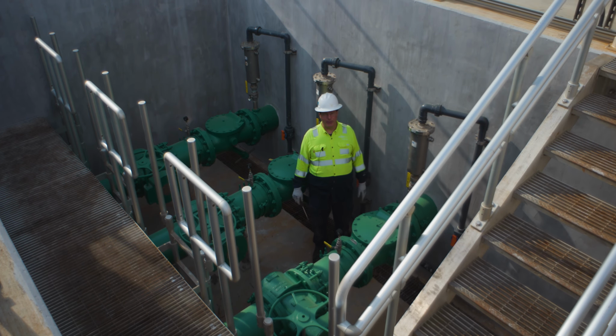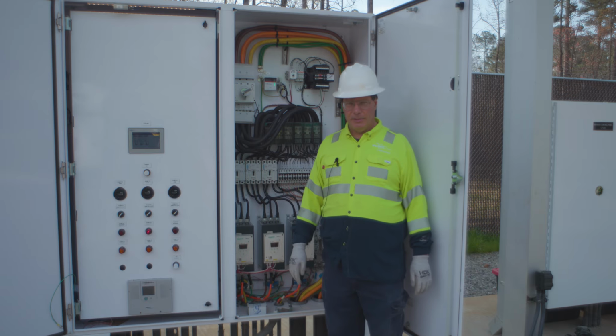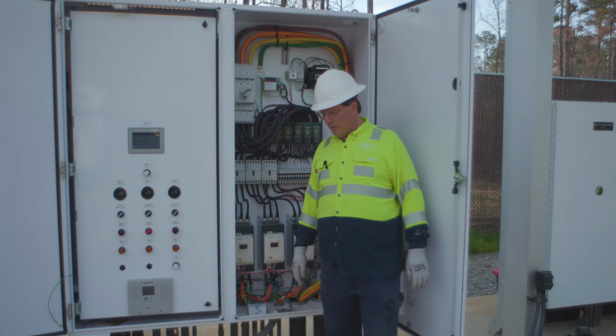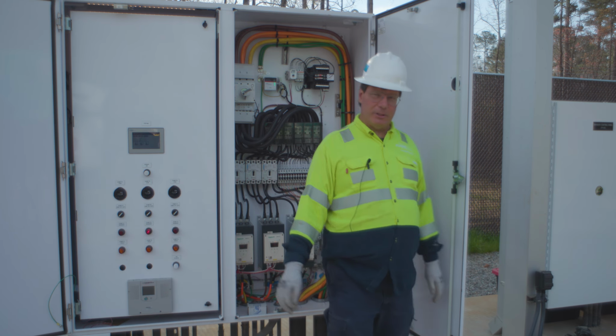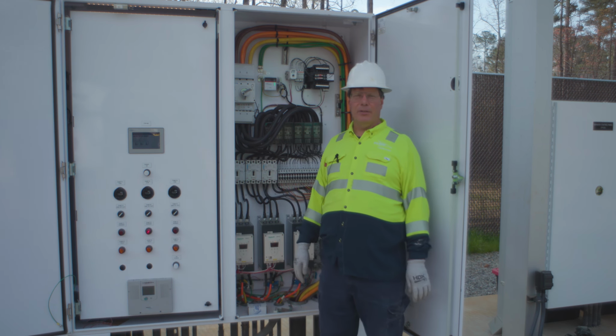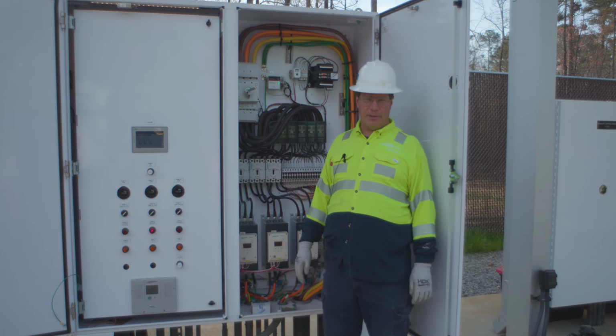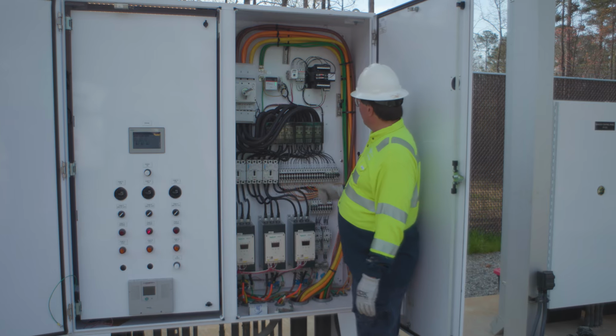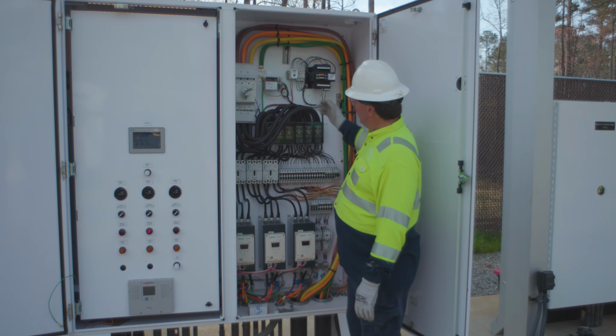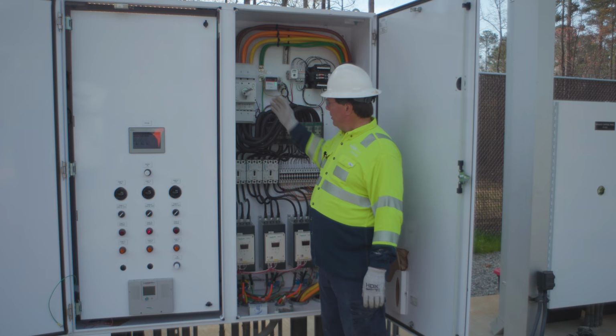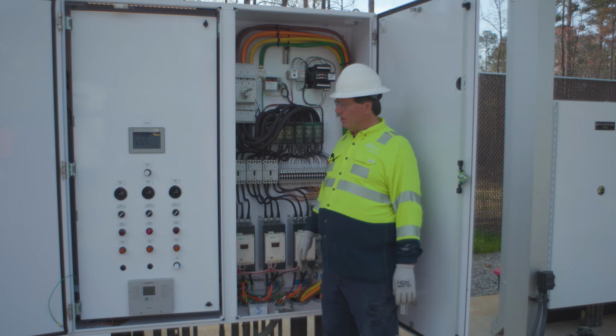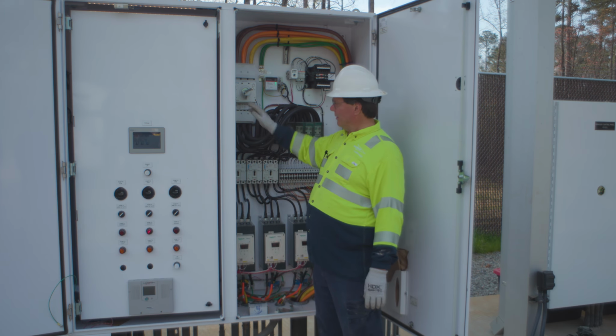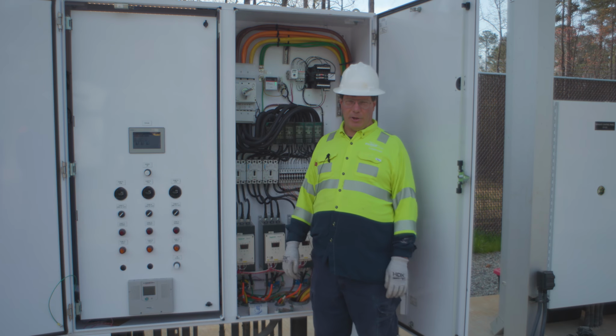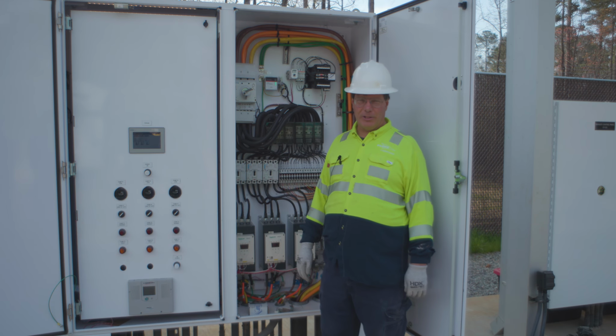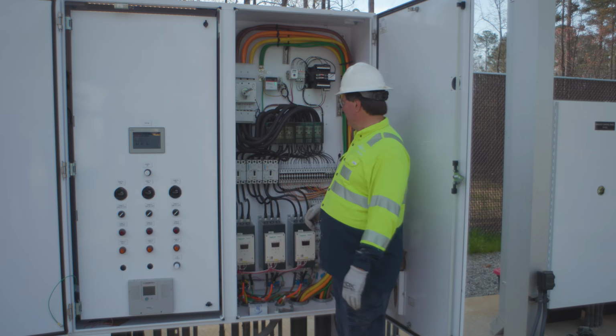Going over the panel, the colored wires are your main power coming in from the service disconnect. The service disconnect is right next to the transfer switch, and they'll go over that in the generator video, so we're not going to cover that here. From the service disconnect, we go to this main breaker. It's a 600 amp main breaker, and it's got all sorts of settings on it based on how much the current has to go up before it'll trip, how long it'll take, and that sort of thing.